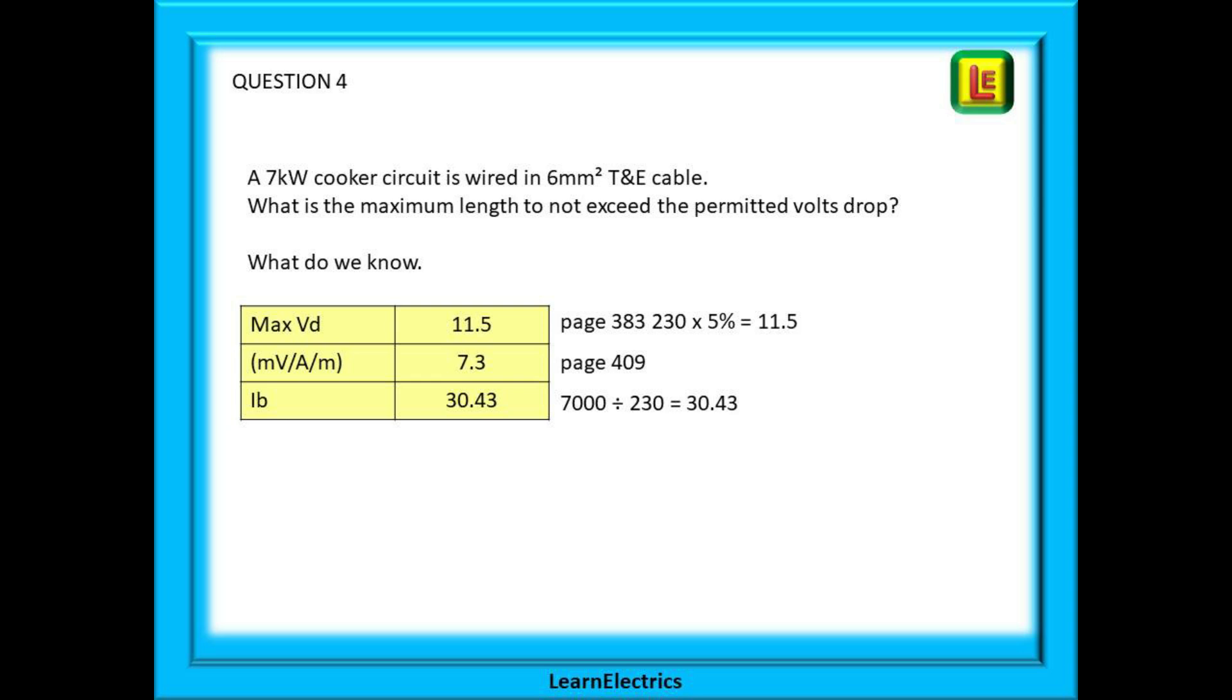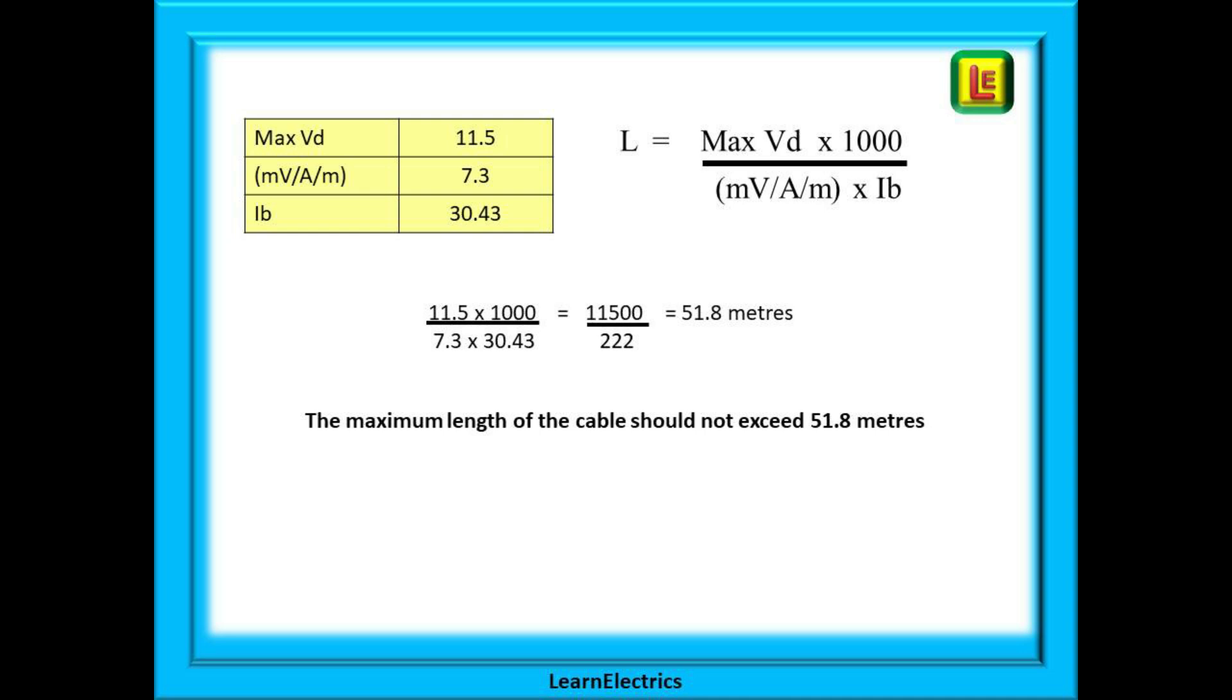Question 4. A 230 volt seven kilowatt cooker is to be wired in six millimeter twin and earth cable. What is the maximum length of cable to not exceed the maximum permitted volts drop? Again, write down what we know as we find it. The maximum volts drop is found on page 383: 230 volts times five percent is 11.5 volts. Page 409 is where we find the mV/A/m number for six millimeter cable, and this is 7.3. And Ib, the design current, is 7000 watts divided by 230 volts to give us 30.43 amps. Run that through the formula and we have 11,500 on the top divided by 222 on the bottom. Our maximum length is 51.8 meters.